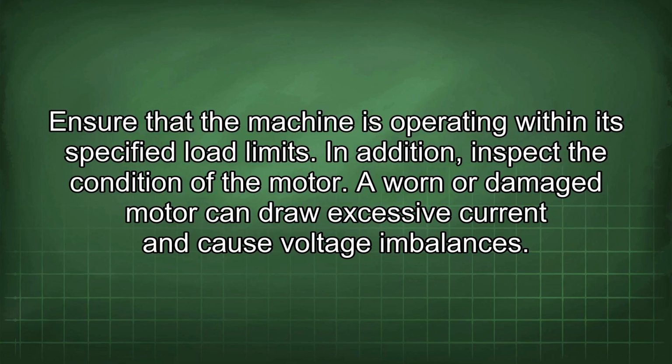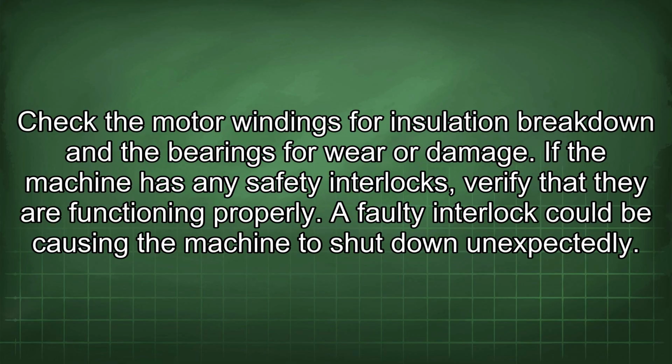In addition, inspect the condition of the motor. A worn or damaged motor can draw excessive current and cause voltage imbalances. Check the motor windings for insulation breakdown and the bearings for wear or damage.